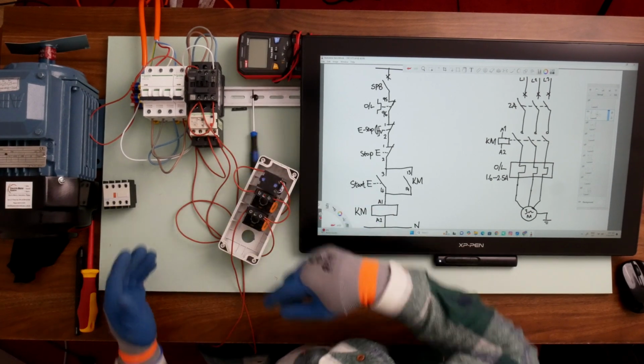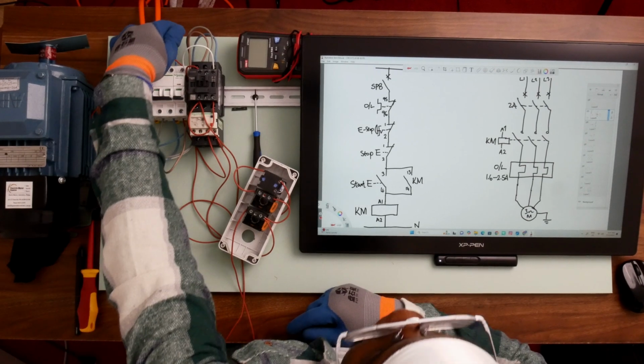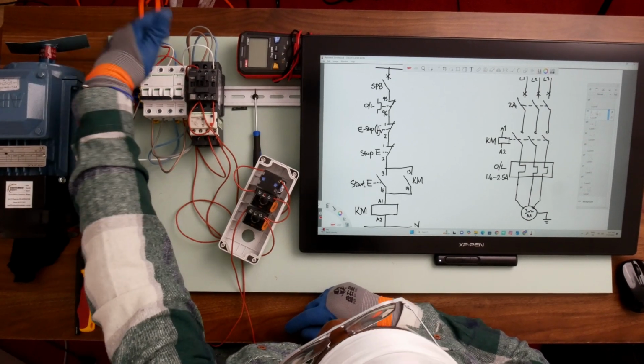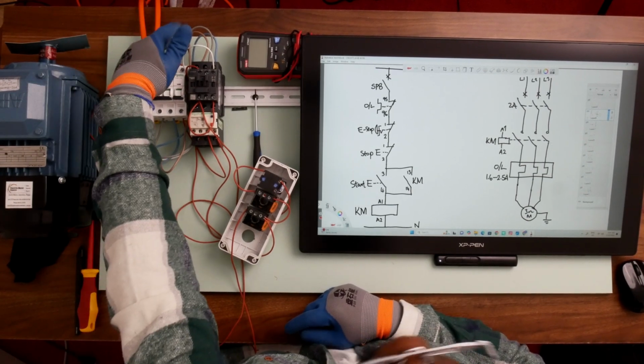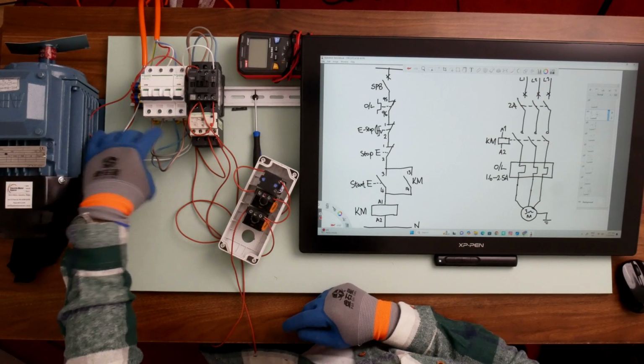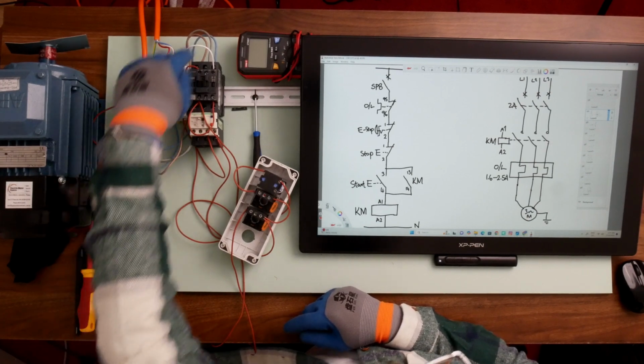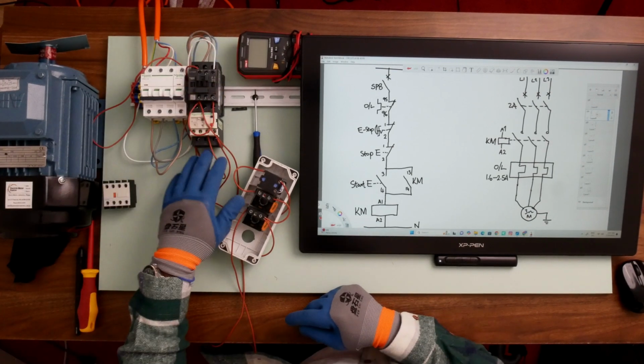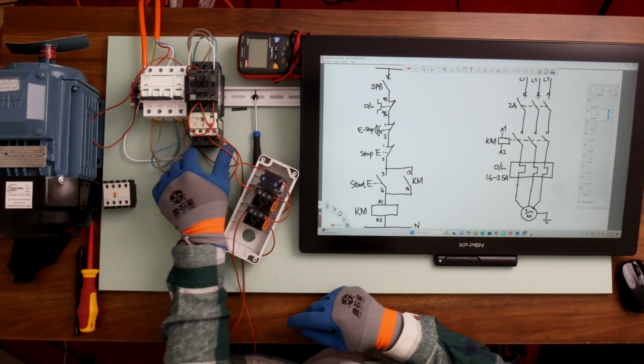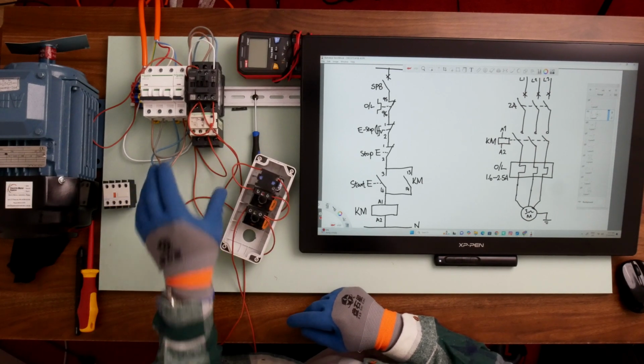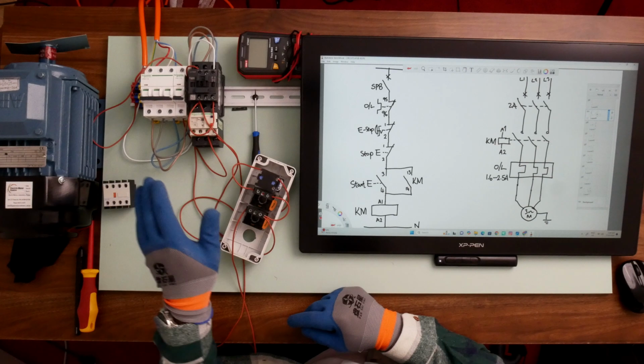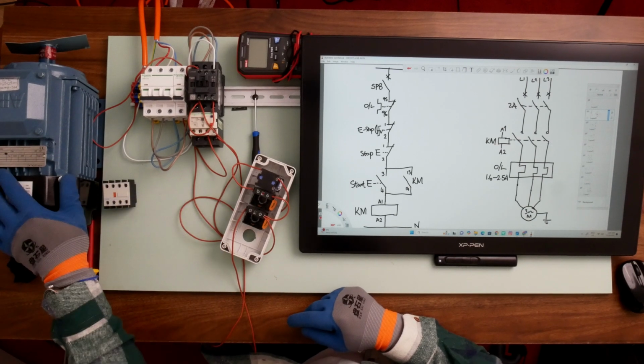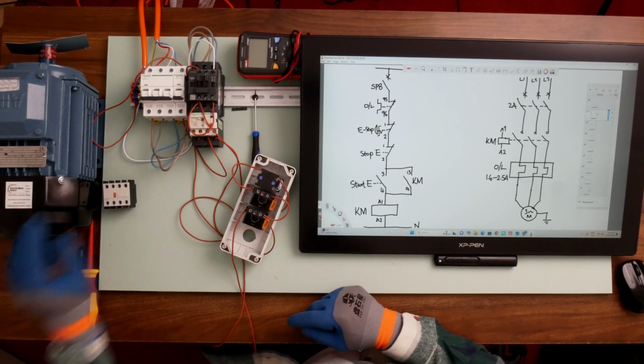And then the power circuit is pretty much straightforward. I have my supply coming in here, red phase, white phase, and blue phase. And then I have this same supply going to the top of my contactor. Now I need to connect my electric motor to the bottom of my overload relay, and then I'll be done with the power circuit. And also make sure that I properly connect this electric motor to earth as well.